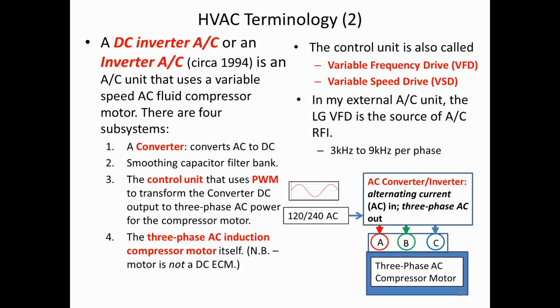So the good news about inverters is you have an AC compressor which has almost continuous range of speeds, and that makes it very efficient if you're trying to adjust the speed to how hot or cold it is. The bad news is there's a pulse width modulator under the hood, potentially creating lots of harmonics. LG said their inverter was within specification, but that wasn't helpful in solving my problem, and I'm going to explain what I did.